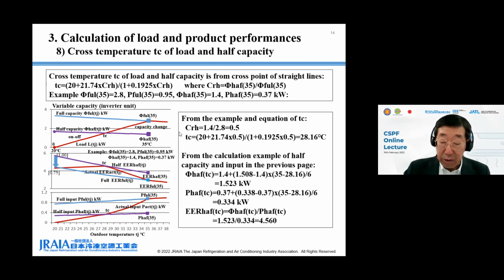Referring to the equation in the example of cooling half capacity and input in the previous page, half capacity at Tc becomes 1.523 kilowatt, and half input at Tc becomes 0.334 kilowatt. Half EER at Tc is half capacity 1.523 kilowatt divided by half input 0.334 kilowatt, equal to 4.560. Next, please.